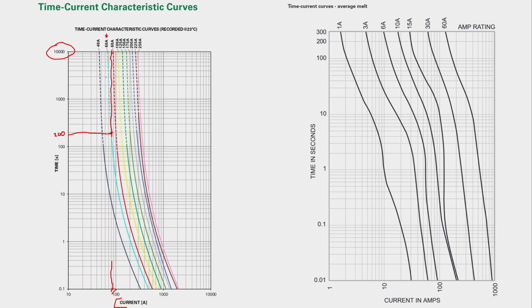Now we have to differentiate between normal load and an overload or an unwanted condition, because if I choose a fuse that is too low and the curve is sitting like this, what will happen is that just under normal load conditions, say the inverter is running at 500 watts, then we see that the fuse is melting, and that we don't want. So we've got to have a fuse that will melt at a current that is above the normal working conditions, but low enough that it can still cater for an overload if that's what I'm protecting. If you're protecting against overload, well, then you will look at the overload current.